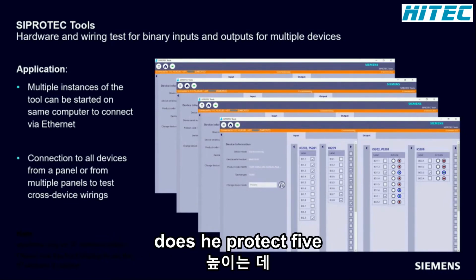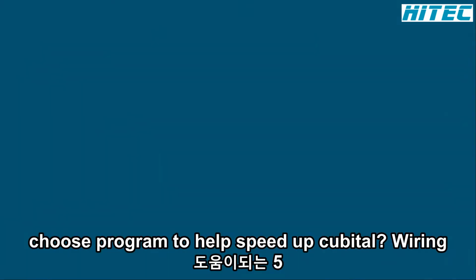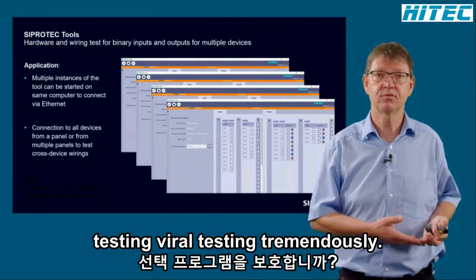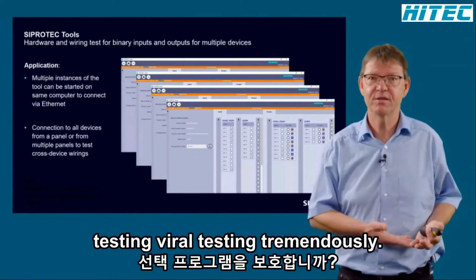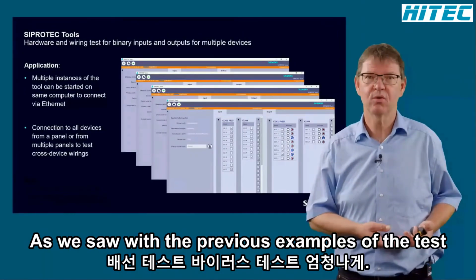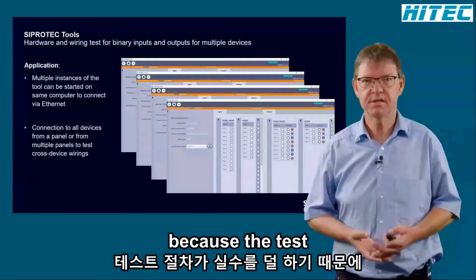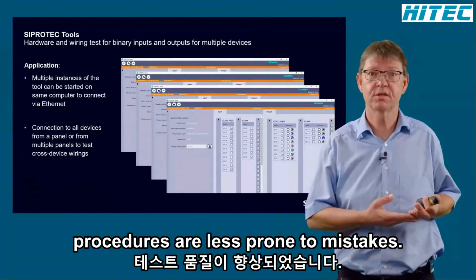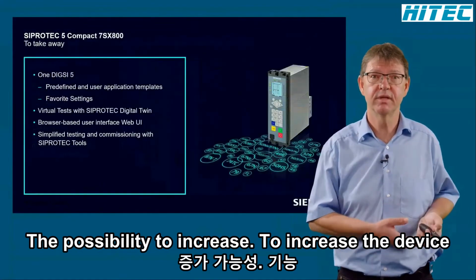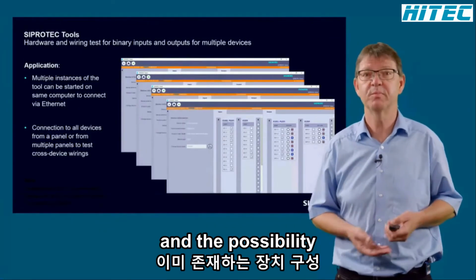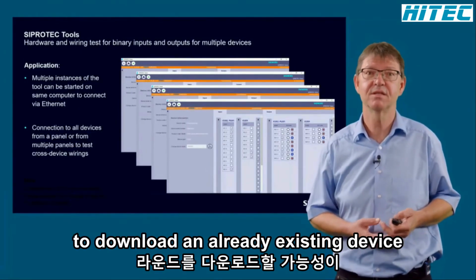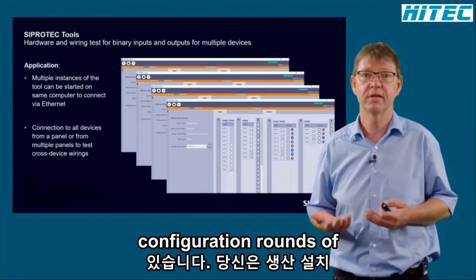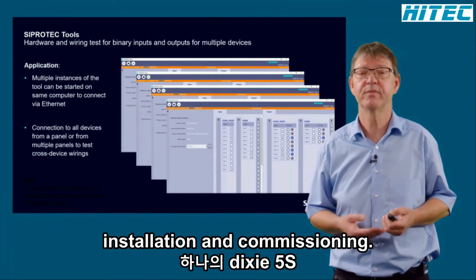Summing up, the SIPROTEC 5 tools program helps speed up cubicle wiring testing tremendously, as we saw with the previous examples. Moreover, the test quality is increased because the test procedures are less prone to mistakes. The possibility to increase the device number of function points and the possibility to download an already existing device configuration rounds off the help during cubicle production, installation and commissioning.